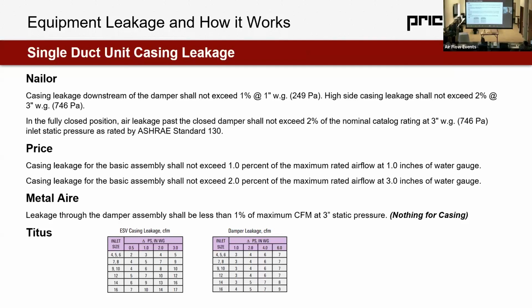Thanks. So on screen here, I have a couple different spec items from a few different manufacturers. The first is Nailor. So the big takeaway with Nailor, and when we compare it and look at it in comparison to Price, it's really the same thing. And it's based off of that ASHRAE recommendation of 2% leakage for 1-inch pressure class, low pressure ductwork. So Nailor and Price manage it the same way, 1% at 1 inch of pressure, 2% at 3 inches of pressure, tested in accordance with ASHRAE standard 130. We do the exact same thing at Price.